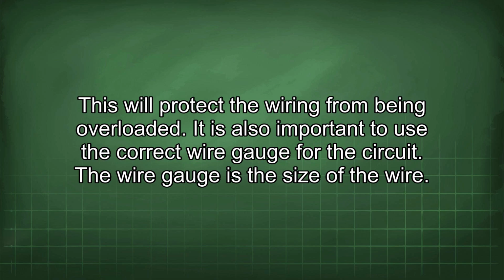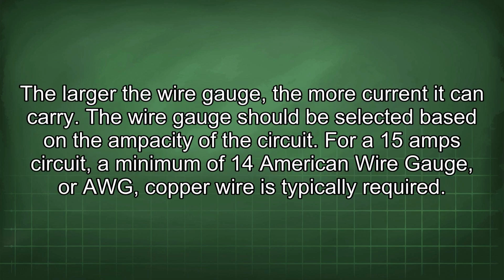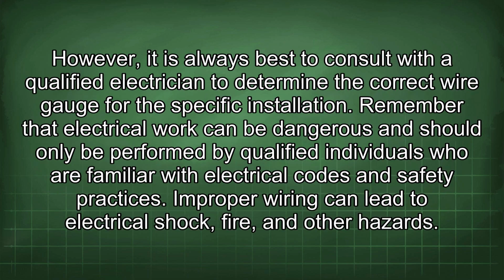It is also important to use the correct wire gauge for the circuit. The wire gauge is the size of the wire. The larger the wire gauge, the more current it can carry. The wire gauge should be selected based on the ampacity of the circuit. For a 15 amp circuit, a minimum of 14 American Wire Gauge, or AWG, copper wire is typically required. However, it is always best to consult with a qualified electrician to determine the correct wire gauge for the specific installation.